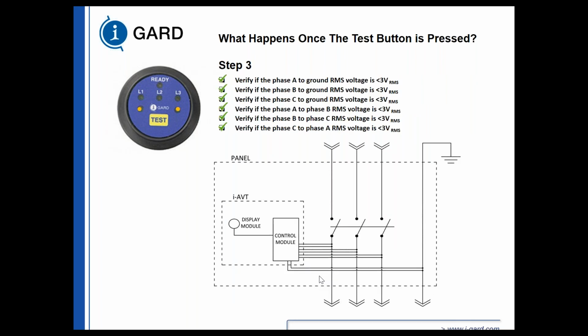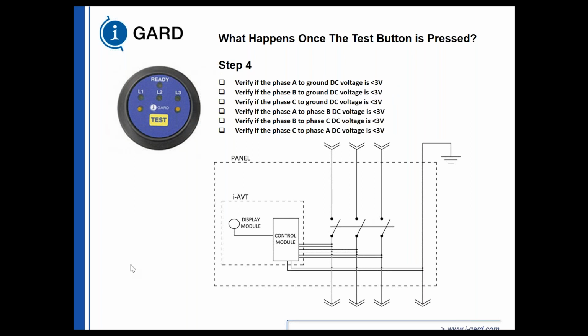Step 3. Verify that the voltage A to ground, B to ground, and C to ground is below 3 volts AC, and A to B, B to C, C to A is less than 3 volts AC. Step 4, verify that the voltage A to ground and B to ground, C to ground is less than 3 volts DC, A to B, B to C, and C to A is less than 3 volts DC.